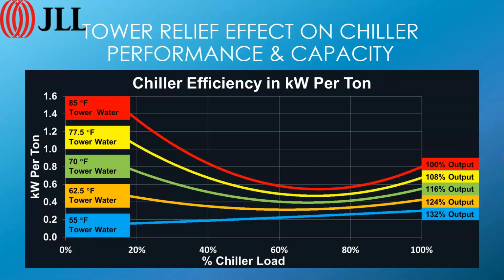As the condenser water gets warmer and warmer because of the ambient conditions, we're going to start to think about having that switch up point move back. Instead of switching up at 95% at 55-degree tower water, we'd tend to switch it at 70% or so with 85-degree tower water. So we're just taking advantage of that additional cooling capacity that Mother Nature's given us.